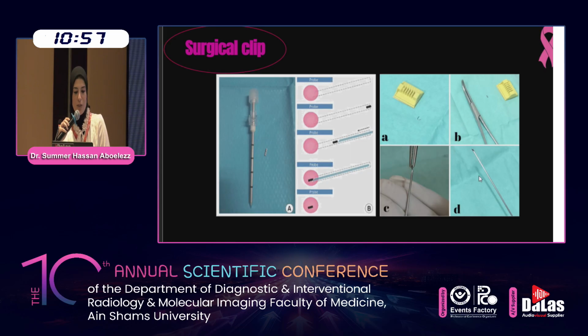We start with the surgical clip. It's simply made of pieces of titanium, and is cheap and widely available. We bring it in a cartridge like this, open the clip and handle it with a sterile holder, bend it manually, and introduce it to the lesion via an angiocath.